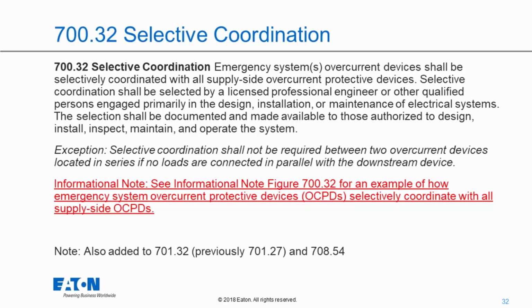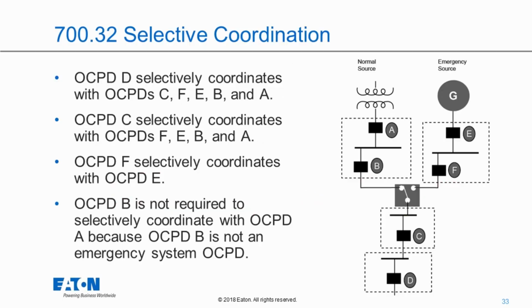So it says, see informational note, Figure 700.32 for an example of how emergency system overcurrent devices must selectively coordinate with all supply side devices. If we go to the figure, we gave a typical example of an emergency system. Let's say that device D supplies emergency loads, perhaps exit lighting. The emergency definitions by the scope of Article 700 include the devices that supply the emergency load all the way back to the alternate source for the emergency system. So the devices classified as emergency system devices are devices D, C, F, and E. The normal source devices are B and A. They do supply emergency system loads, but they're not in the path to the alternate source of power.